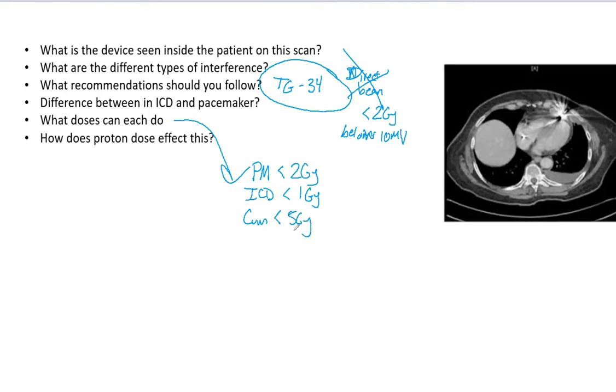So the protons, how does that affect these pacemakers? You don't want any dose rate greater than 800 centigray per minute, because that will cause 70% failures. Neutrons cause devastating damage and protons are dangerous because of the recoil neutrons. So something you have to be very careful about.